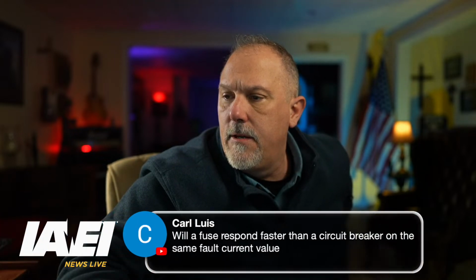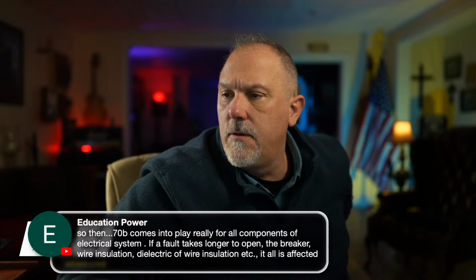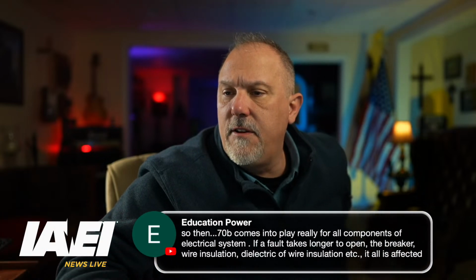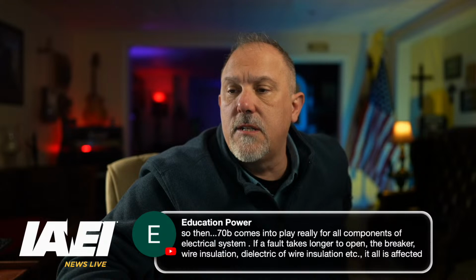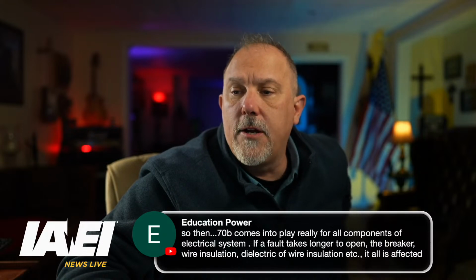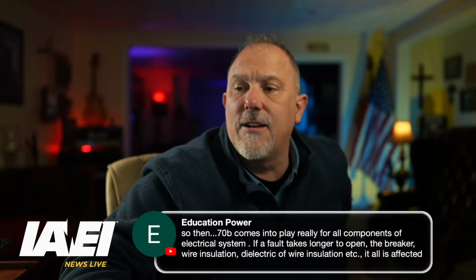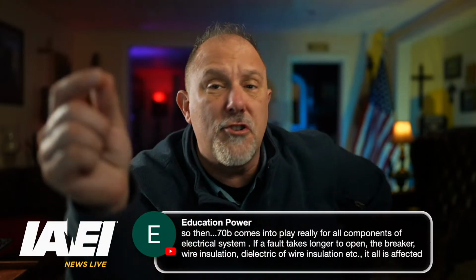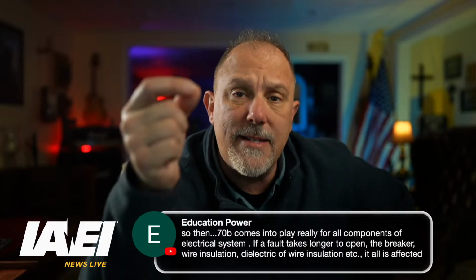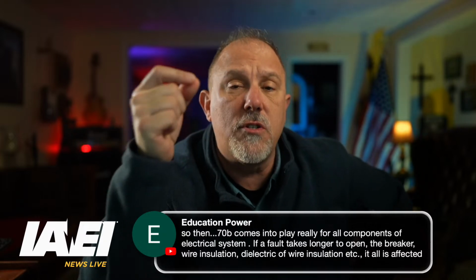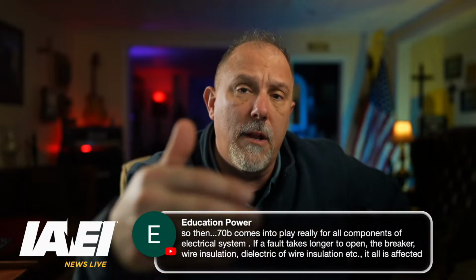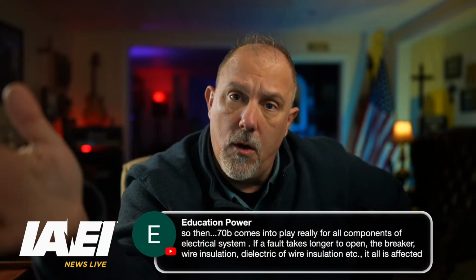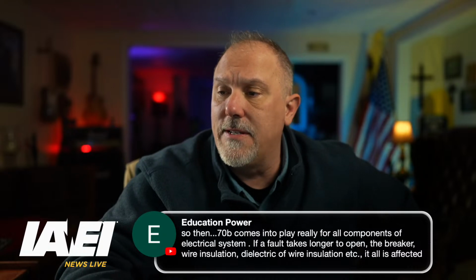Jason, yes, and you can use that for 70. Let's go back up. I heard a bunch of, I got 110.9, I got withstand. I got the will of fuse. So then, 70B comes into play really for components of electrical systems. If a fault takes longer to open the breaker, wire insulation, dielectric of wire insulation, etc., all absolutely, and all your components, all your terminations, Robert, the stress that's placed on the power distribution system because of fault currents, the longer you let those fault currents flow, the more stress you're putting on the system in general.